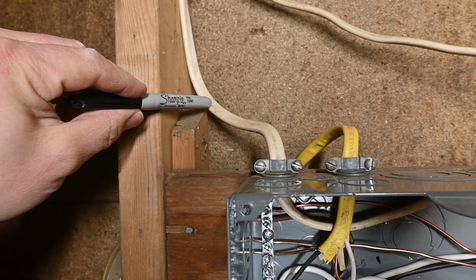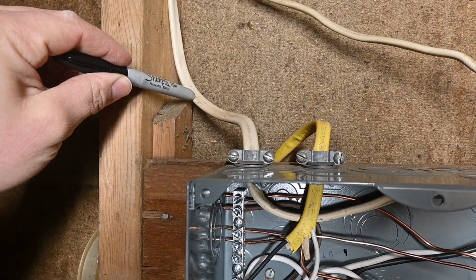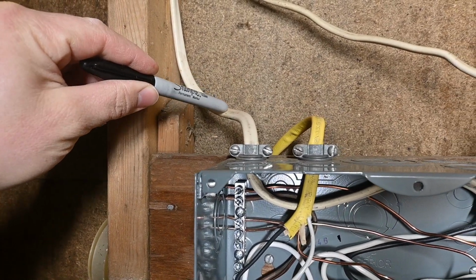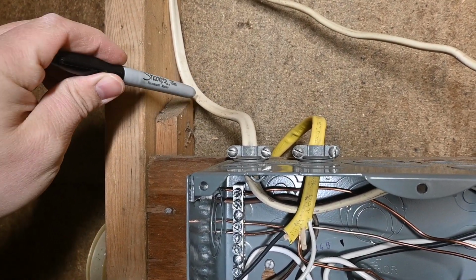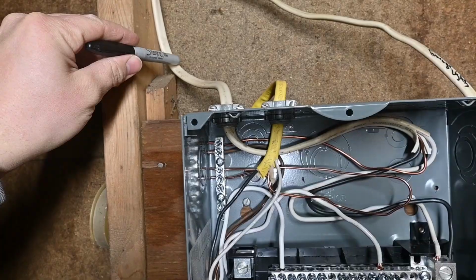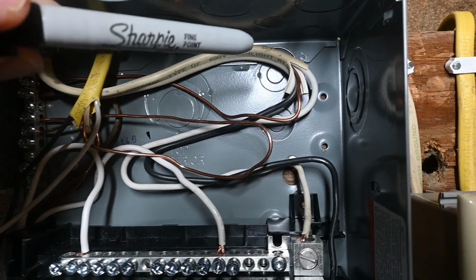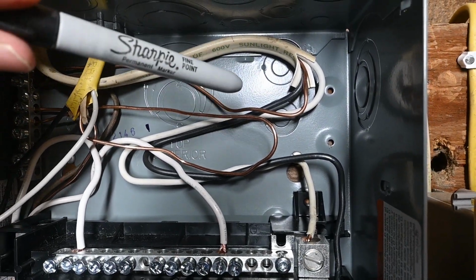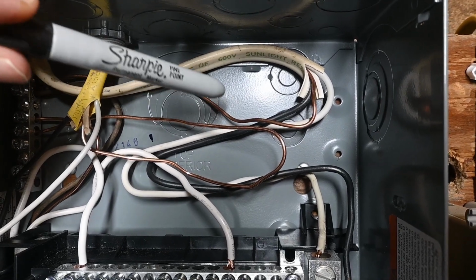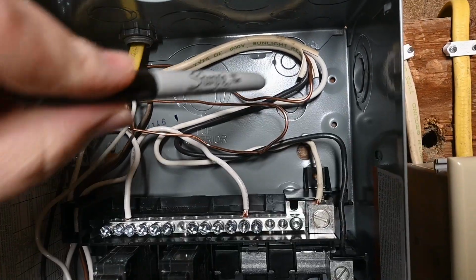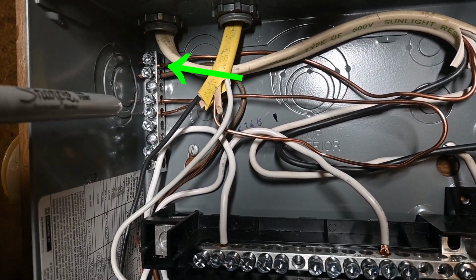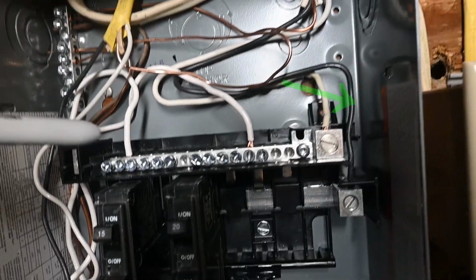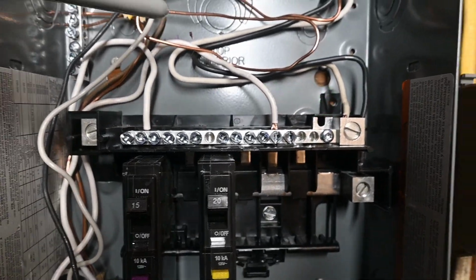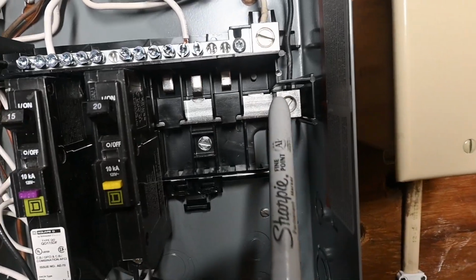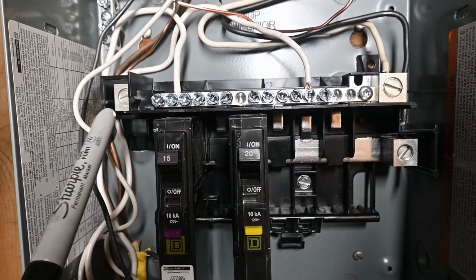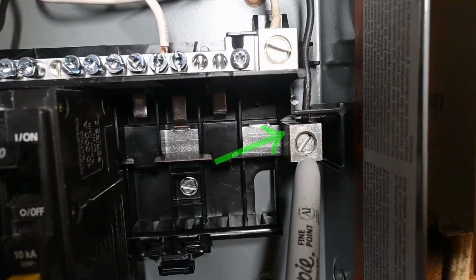Here at the top we have a piece of 12-2 with ground cable that is feeding this panel. This is a 120 volt circuit that is being fed by a 20 amp breaker back in the main panel in the house. This wire comes down into the box, and you can see once it gets stripped back over here that we have a bare ground wire, a black hot wire, and a white neutral wire. The ground wire goes over to a dedicated ground bar here in the corner. The neutral goes to our neutral bus right here, and then our hot wire goes to one of the two spots where your 240 volt legs would normally land. So we've got it landing over here on this leg.